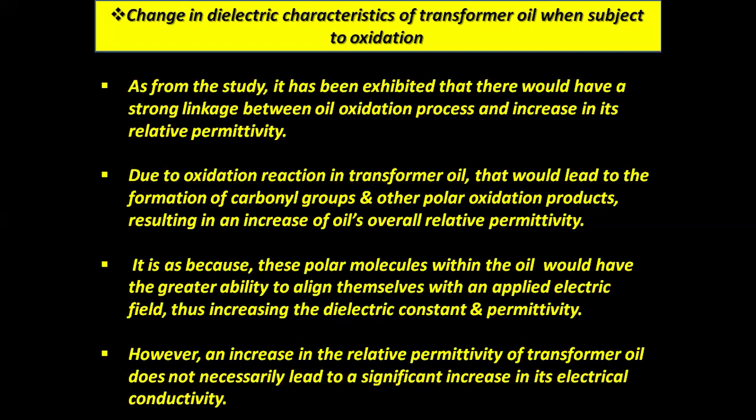Due to oxidation reactions in transformer oil, carbonyl groups and other polar oxidation byproducts form, resulting in an increase of the oil's overall relative permittivity.